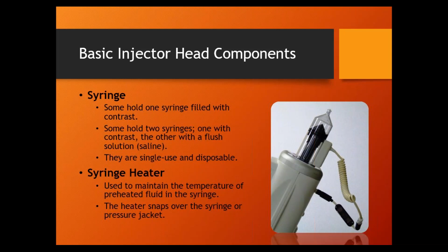But angio injectors always have one. Some CT injectors have both. Actually, nowadays most CT injectors have two. If you have a CT injector and it's just one syringe, then it's most likely either being used at a vet clinic or on a single slice. But do those even exist anymore, single slice CTs? I don't know. But like 4 slice and 16 slice CTs. I mean, if you have a 64 slice CT system, for the quality of the images that it's going to produce, you need a dual head CT system. There's no point in having a single head CT injector on a 64 slice or better CT system. It's going to be a dual head CT injector. And to be honest, over 90% of all CT injectors are dual heads. There's not that many single heads out there. There are, but not nearly as many as dual heads.